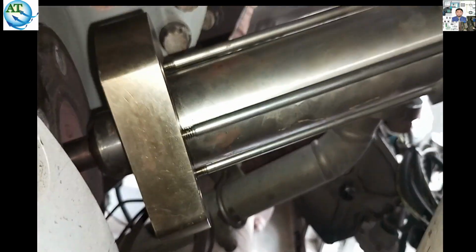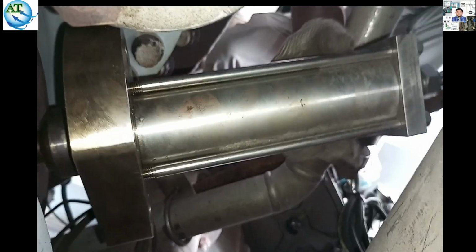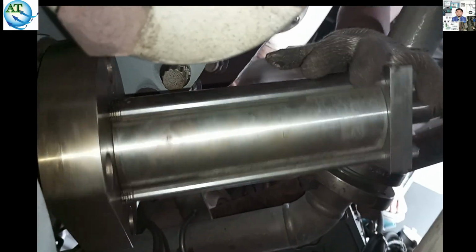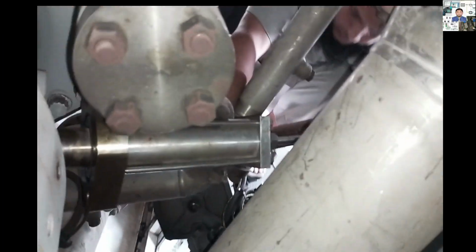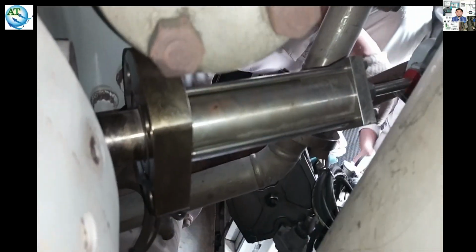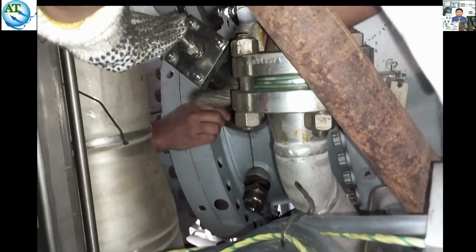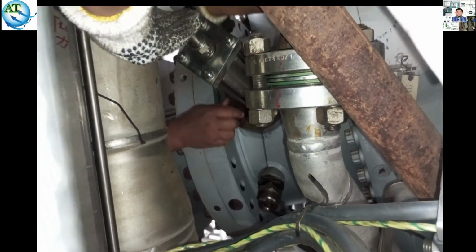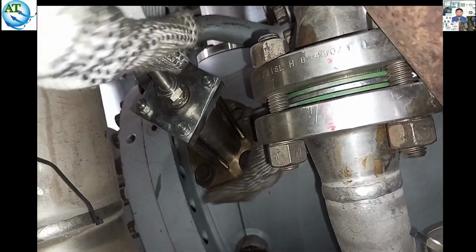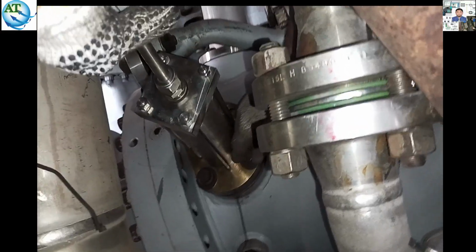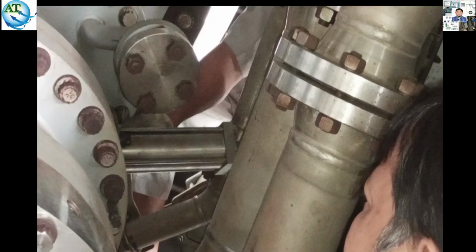So we are connecting the new igniter. You see, we are inserting the new igniter. We have connected this one properly. Then we try to start the turbine. In this gas turbine we are using two igniters, and we found that both igniters have been faulty, and we are finding that it is getting more ohms.